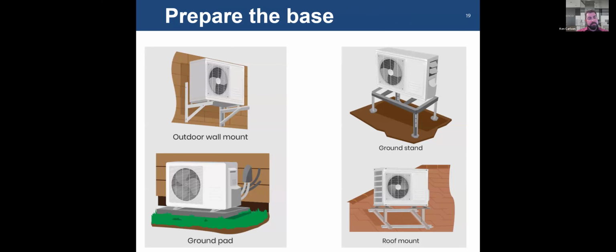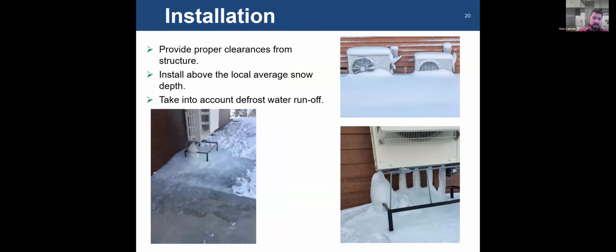If you're in a cold climate where you have any amount of snow, you're probably not putting your heat pump on the ground, or you're going to be burying it in snow. So the outdoor wall mount is probably the most common, or even a ground stand will suffice with enough height and clearance for local snow height. Depending on the area, you have to go to your local code officials to figure out what the actual snow line is, right? As far as what you design for, depending on where you're at, it could be a foot, 2 feet, 3 feet. Understand and know what it's supposed to be. Avoid sides of the house that are going to get a snow drift. Just a piece of advice. So make sure you've got your proper clearances from your structure and snow depth.